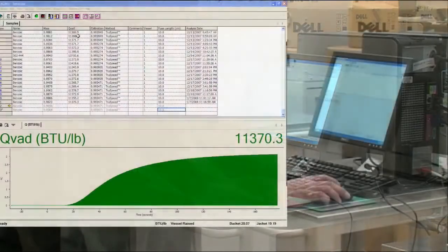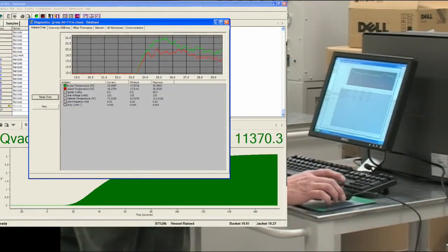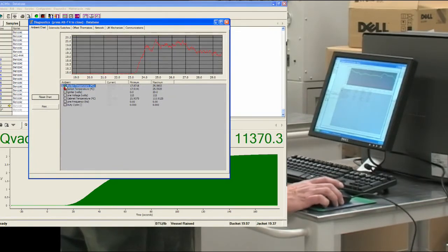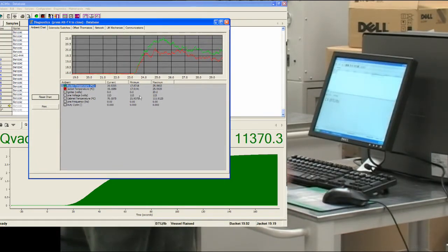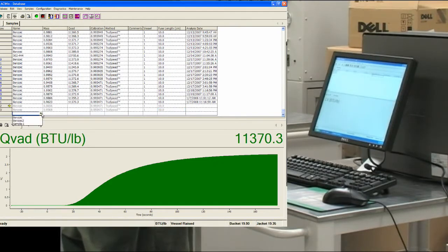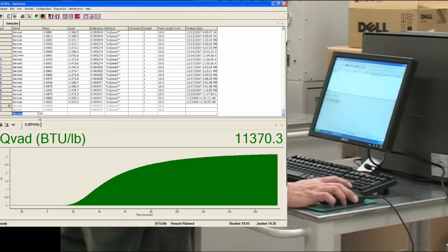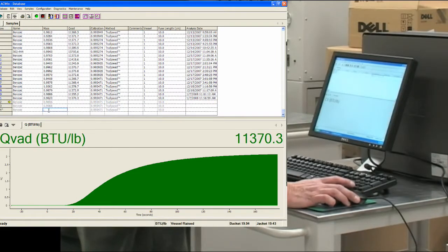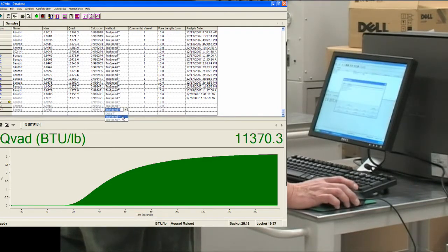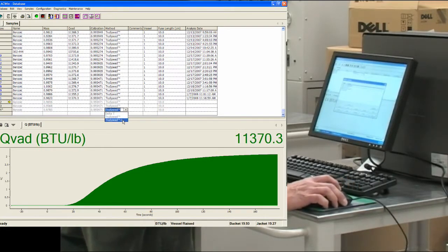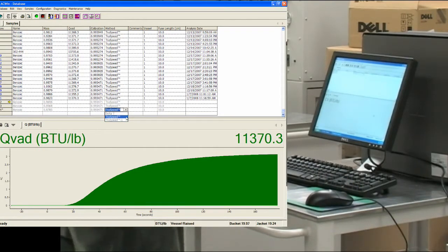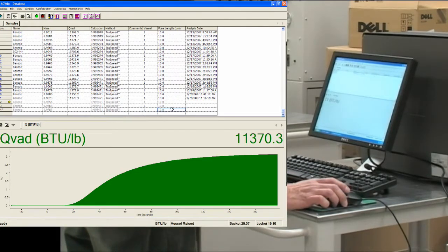And how you can check the stabilization is go to your diagnostic screen on their chart and make sure your temperatures appear to be stable. If they're nice and stable, you're ready to proceed with running an analysis. What you would like to do first is run several benzoic acids to do a calibration. Under the name, you would log in your sample name, weigh up your sample, enter the mass, and choose the method. You have 2 methods available to choose. One is TruSpeed, which is the recommended method, and the other method is delta T. You can also design your own methods, but we have found that the TruSpeed is a very adequate method to be using. You want to make sure your fuse length is set at 10. You're now prepared to run an analysis.